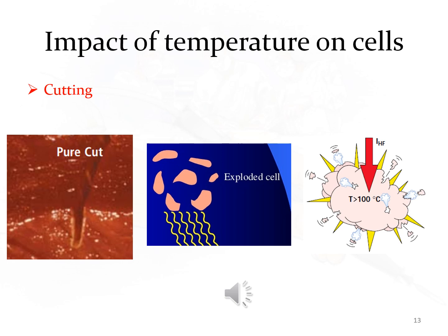Electrotomy, or cutting. High-frequency alternating current can be used to rapidly heat the target tissue to temperatures above 100 degrees, so that vapor pressure explosively ruptures the cell membrane. The sum of many small cell explosions creates a cut. Rapid heating of tissue massively increases the vapor pressure, leading to the explosive rupturing of the cell membrane.